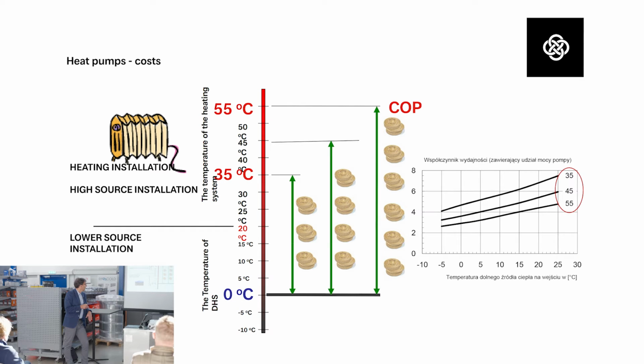Pretty much the same story applies to the high heat source side. If we have a lower running temperature, a lower supplying temperature of the installation, we have a high COP factor. So our goal is to keep as low a temperature as possible on the outlet from the heat pump to provide efficient heating, for example with floor heating or wall-mounted heating. The lower the temperature on this side, the higher the savings, so low operating cost. If we connect this device to high temperature systems, for example radiators or fan coils, we can spend much more money on operating cost.